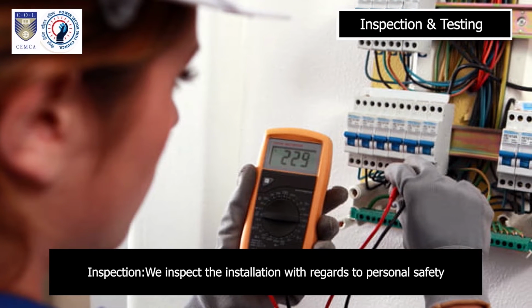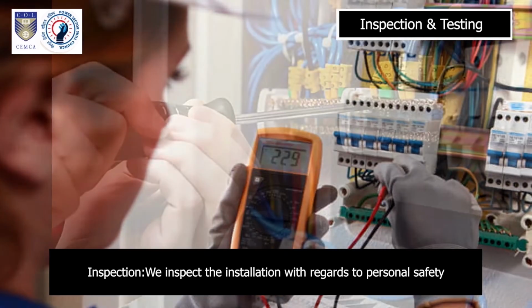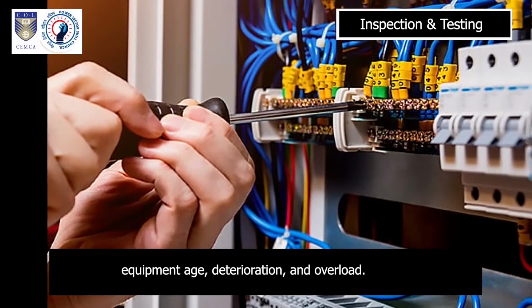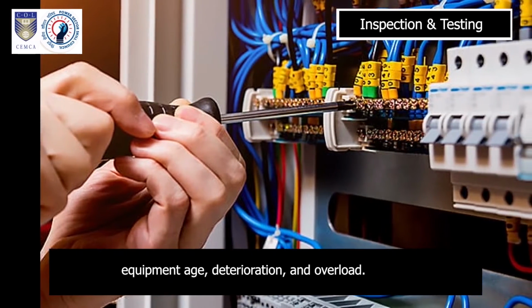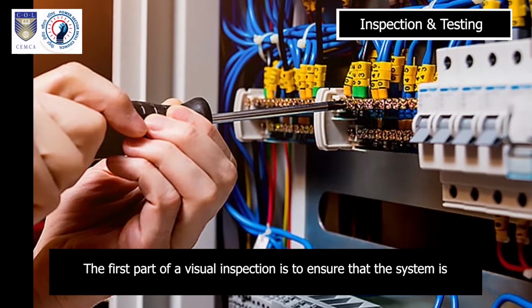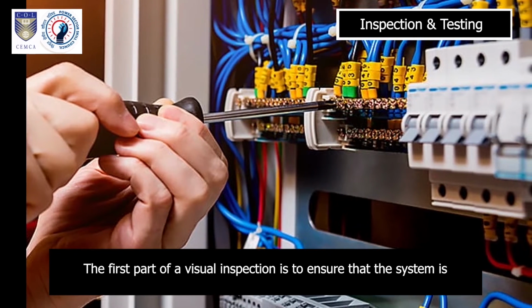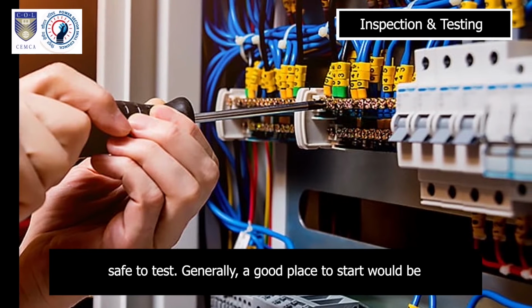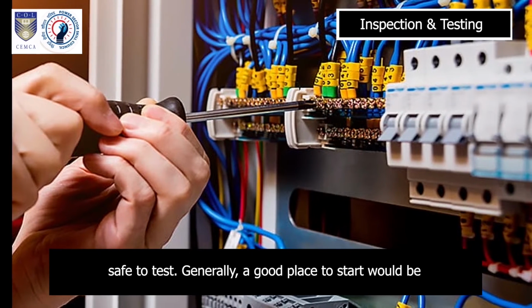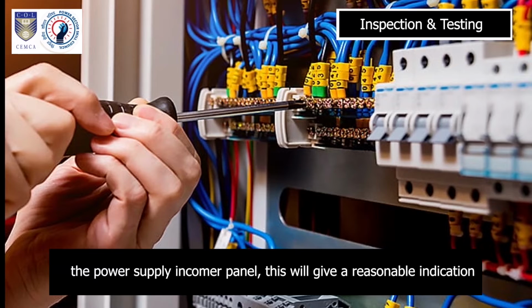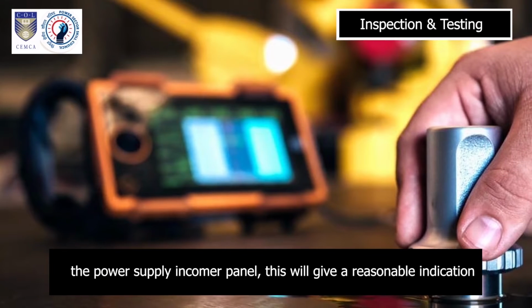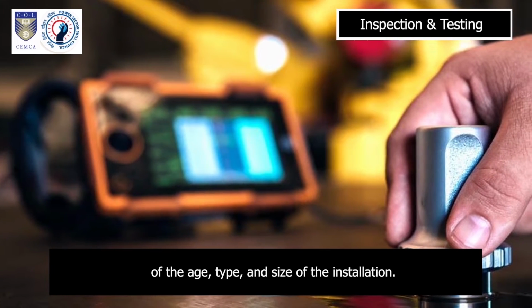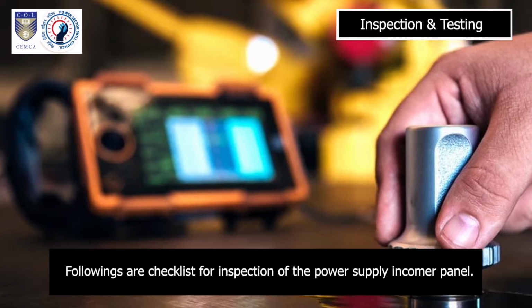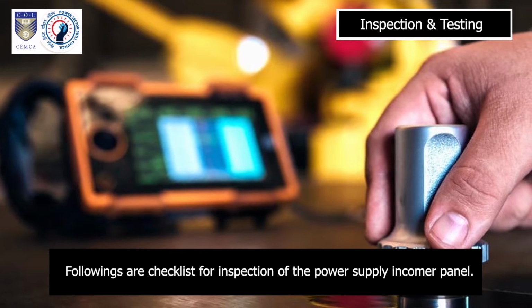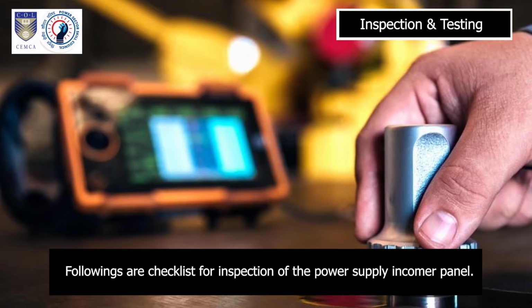Inspection and testing. Inspection. We inspect the installation with regards to personal safety, equipment age, deterioration, and overload. The first part of a visual inspection is to ensure that the system is safe to test. Generally, a good place to start would be the power supply incomer panel. This will give a reasonable indication of the age, type, and size of the installation. Following are checklists for inspection of the power supply incomer panel.